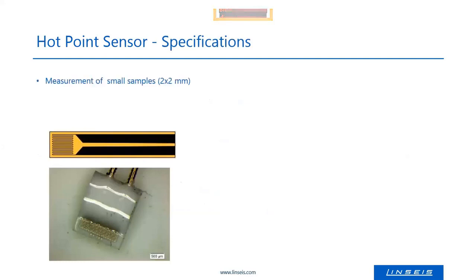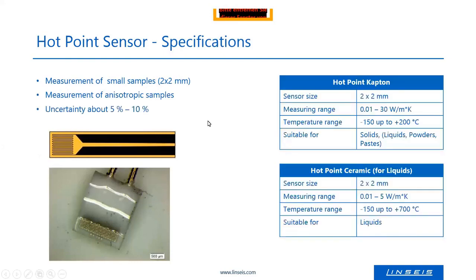The specifications of the hot point sensor: it was designed mainly for small samples down to 2 by 2 millimeters. It can also be used for anisotropic samples, which is quite useful. The uncertainty is between 5 and 10 percent. The measurement range of the Kapton hot point sensor is between 0.01 and 30 W per meter Kelvin, and for the ceramic hot point sensor, it is 0.01 up to 5 W per meter Kelvin.